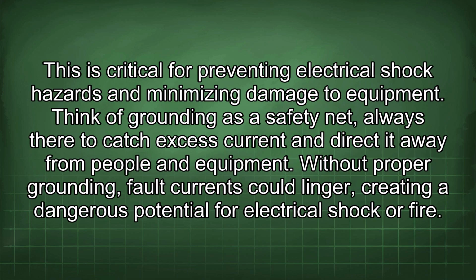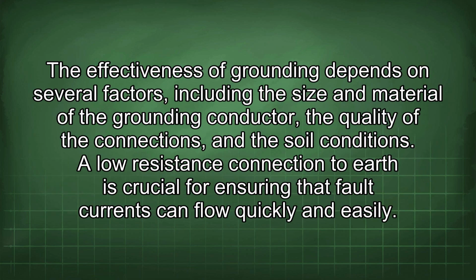This is critical for preventing electrical shock hazards and minimizing damage to equipment. Think of grounding as a safety net, always there to catch excess current and direct it away from people and equipment. Without proper grounding, fault currents could linger, creating a dangerous potential for electrical shock or fire. The effectiveness of grounding depends on several factors, including the size and material of the grounding conductor, the quality of the connections, and the soil conditions.